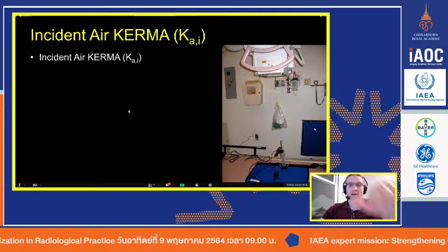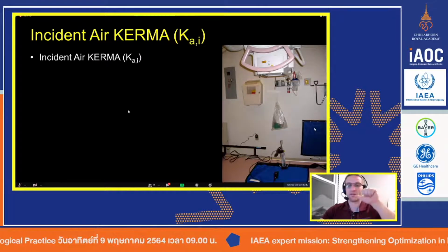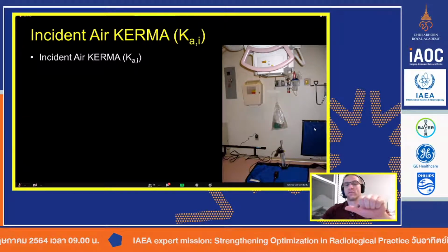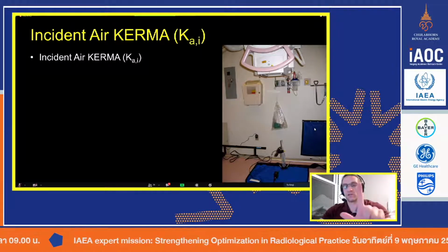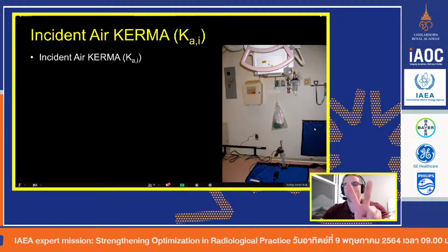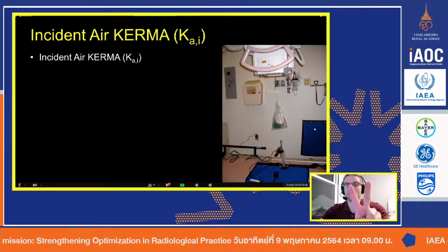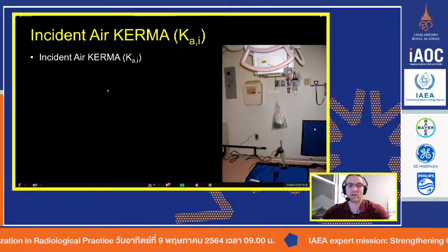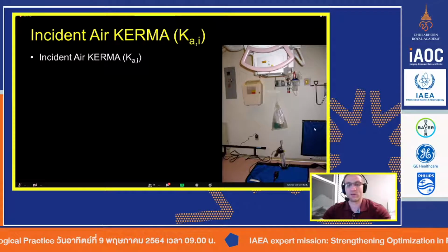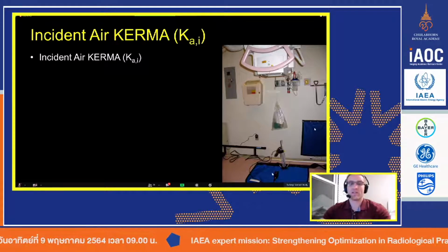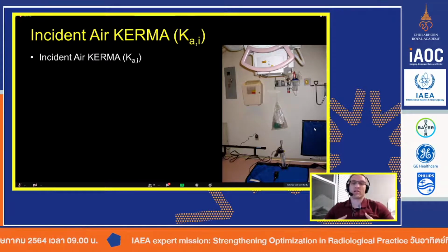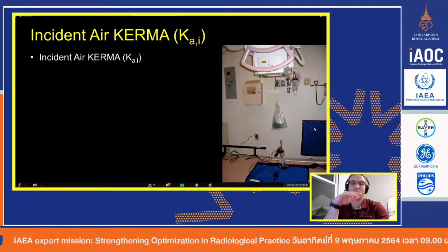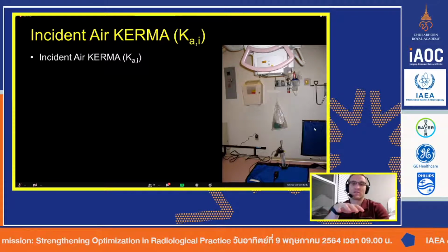All right, so we've talked about dose to the detector. We've talked about the value that we would use clinically, which is still an approximate dose to the detector, called exposure index, or EI. And we've also briefly talked about deviation index and how to calculate it. We'll get into more detail for deviation index next talk. Now, the other metric we had talked about was the incident air kerma, the value that would be at the surface of the body, somewhere in that region, if there was a body in the X-ray beam between the detector and the tube.